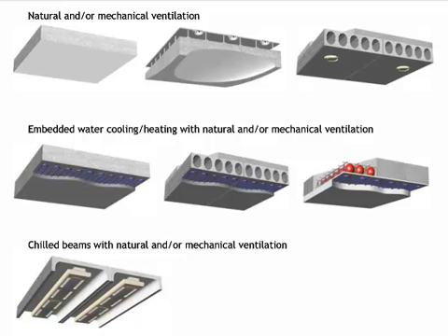More recently, water-cooled soffits have become very popular. Here you've got polybutylene pipework embedded just above the surface of the soffit, supplied with chilled water, quite often from boreholes, which comes up at just the right temperature, about 12 to 14 degrees. You can also use heat pumps and conventional chillers. The advantage of water cooling is you get a higher cooling output and a really good level of control.